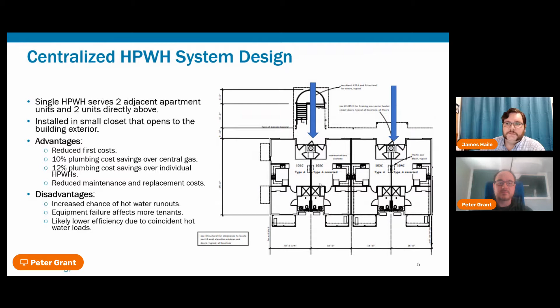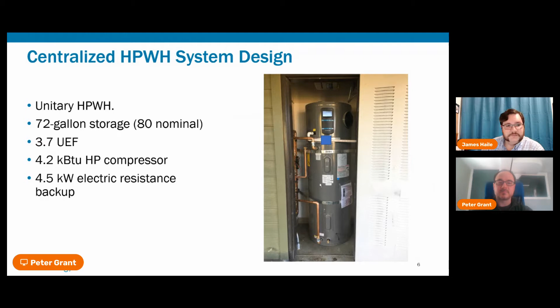This is the heat pump water heater that we used. It's a very basic 80-gallon unitary heat pump water heater with a tiny compressor and about 4.5 kW of backup heat. It's basically exactly what you would think of when someone says unitary heat pump water heater. This is what it looked like installed in the exterior cabinet sans plumbing insulation. The astute members of the audience will probably immediately notice a potential issue that we'll get into in a couple of slides. But that's basically what it looked like.